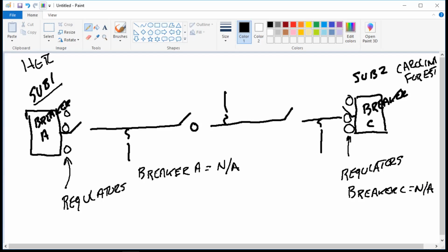Okay. The next step, and there'll be a little bit of description behind this one. Block ground relay, breaker A. Okay, and I'll do the next step because it's the same thing. Block ground relay, excuse me, my spelling. Relay, breaker C. And they'll specify the substation when they have that conversation going on over there. Why do we block the ground relay in both breakers?